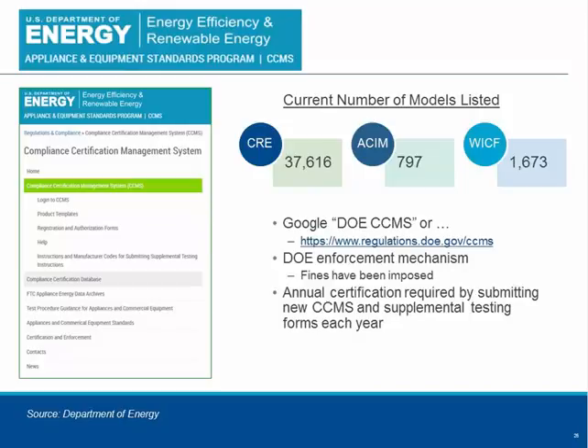Now, one thing I wanted to mention. You see 37,000 reach-ins listed, and they have to be recertified every year. That doesn't mean every single basic model needs to be retested every year. Very often, equipment manufacturers use alternative efficiency determination methods. The Department of Energy does allow equipment manufacturers to use models to rate their equipment, as long as they can defend what they're publishing.